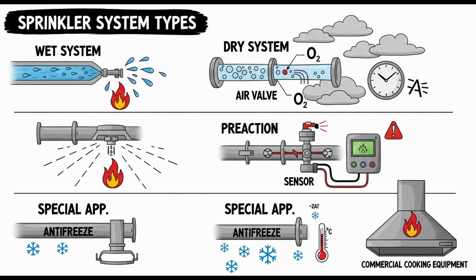Yes, this strict requirement for detection being faster than sprinklers is waived under certain conditions. Specifically, for double interlock pre-action systems, or for single interlock pre-action systems that use an antifreeze solution in the piping, the detectors are permitted to be any type that is specifically listed for use in refrigerated areas, provided they are installed according to their listing and the relevant fire alarm standards, like NFPA 72.